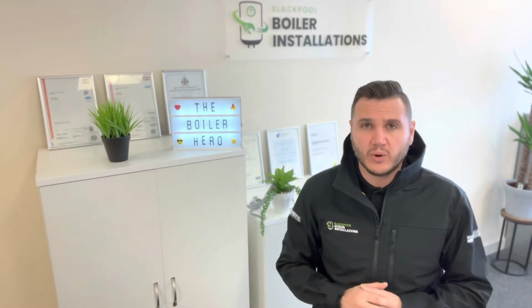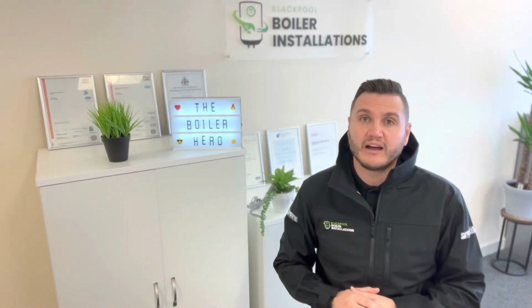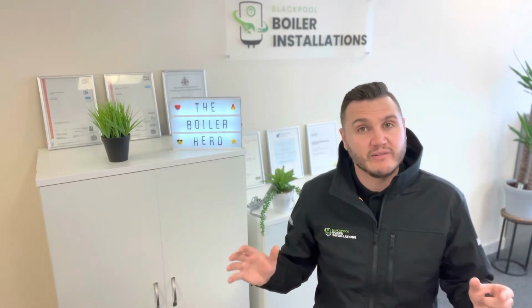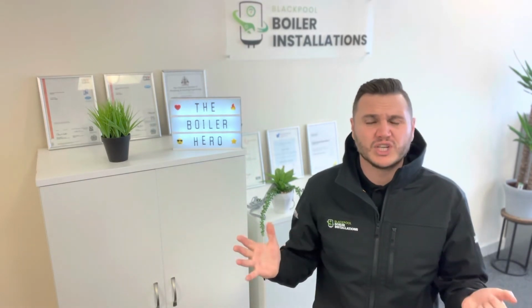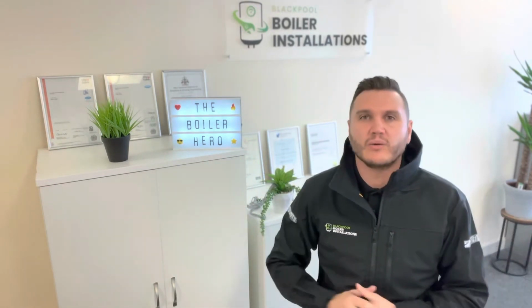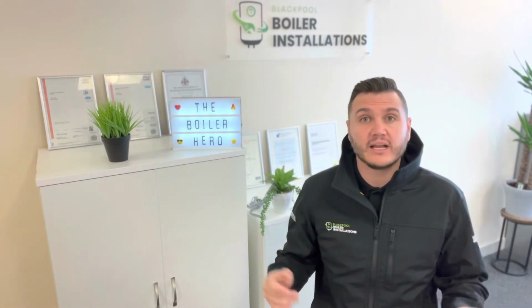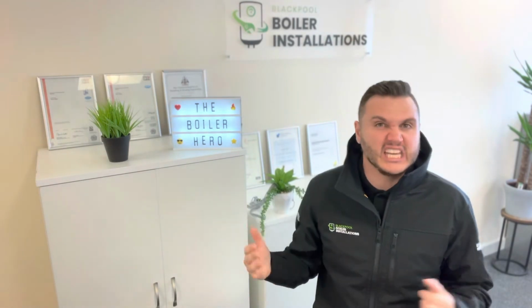Now, this is a rare occurrence, but if a system hasn't been drained for a while and then all of a sudden we come and carry out some work, you could have problems opening up a can of worms on a system, and radiators that have worked before now do not work since you've modernized the system. It is unfortunate when that happens. Obviously we can't be responsible for the entire system just because we're fitting a boiler. We didn't fit the pipework, the valves, the radiators and all the rest of it. So it's just to make you aware that sometimes you can get small issues like that. We'll happily have a look for you, and if it's something we can do or it is something we've done, we can sort it, but you may need some further work that you didn't know about before.